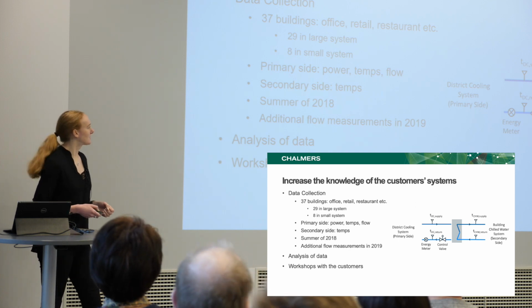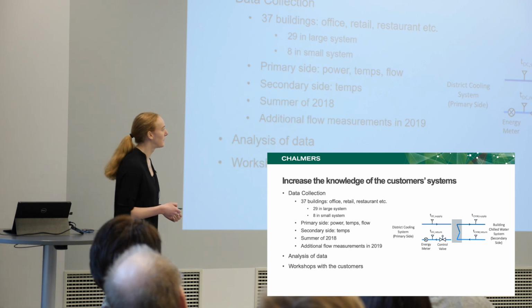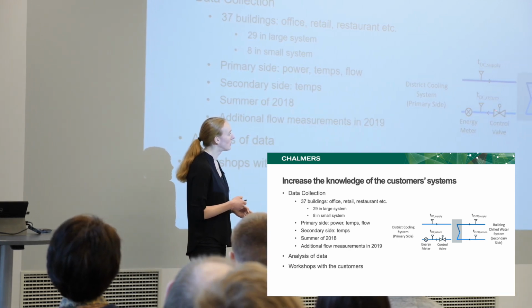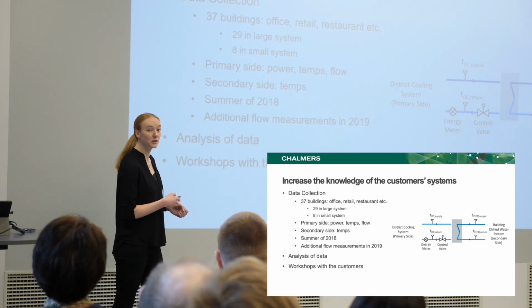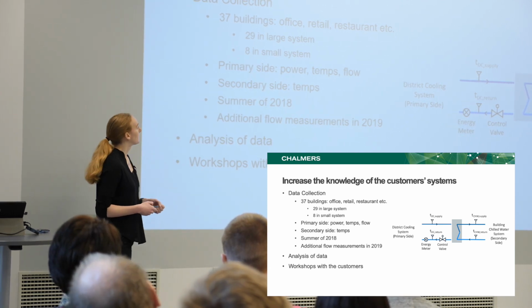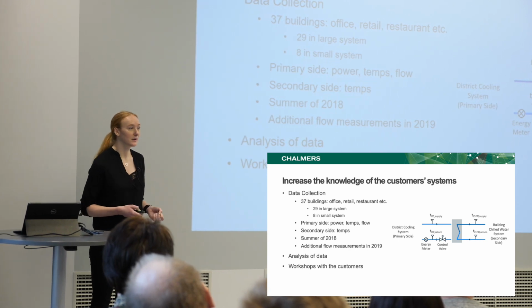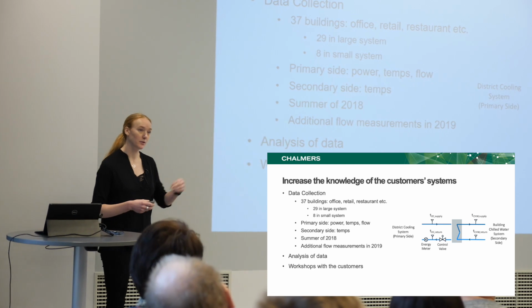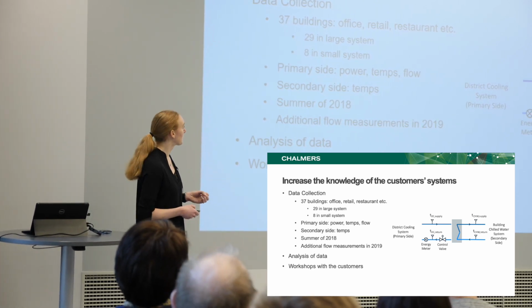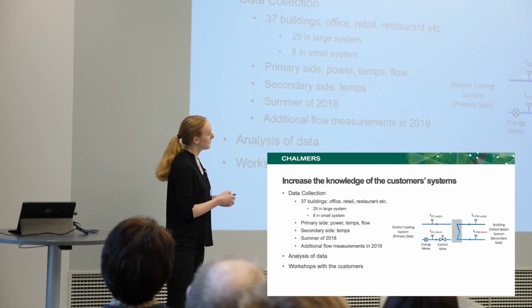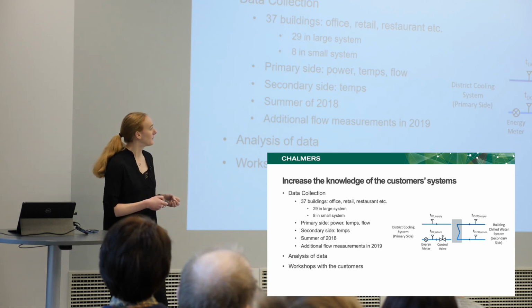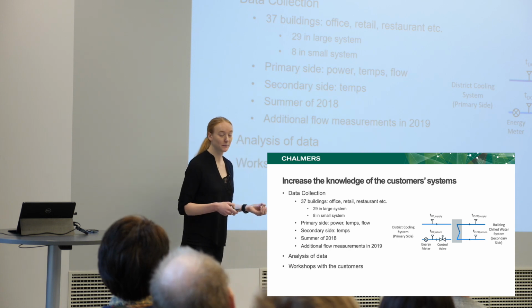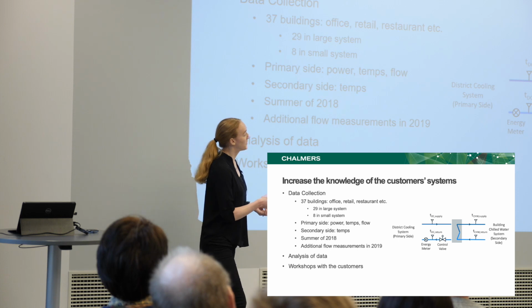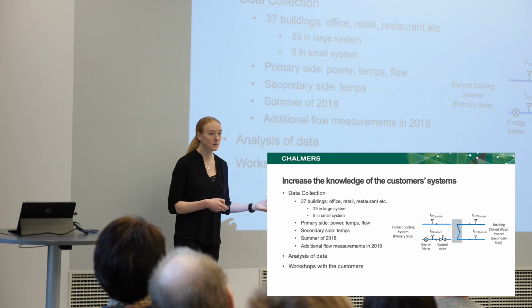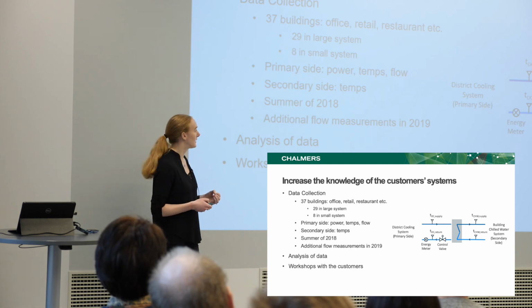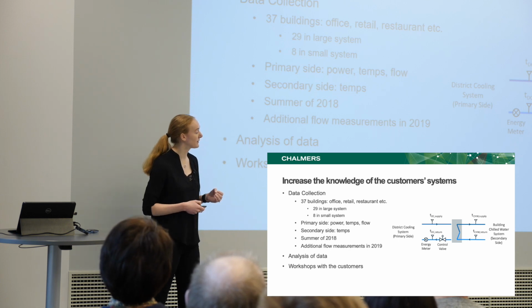And this has been the method so far. I have collected data from essentially the substation, this you already saw, from what the district cooling provider measures on the primary side of the heat exchanger. And I collected data from 37 buildings, it turned out to be in the end. 29 are in the large system and 8 are in the smaller system on the north side of the river. And on the primary side here, what data is available are the temperatures, but also the flow and the cooling power. But I also went into the building owners' building management systems and collected the data that was available on this side, which was a lot of information about the systems and mainly the temperatures that they log there, and also how much they open this control valve.